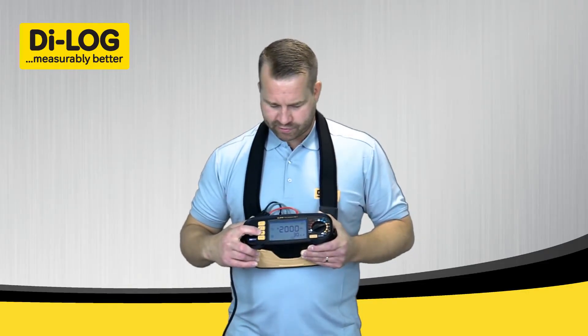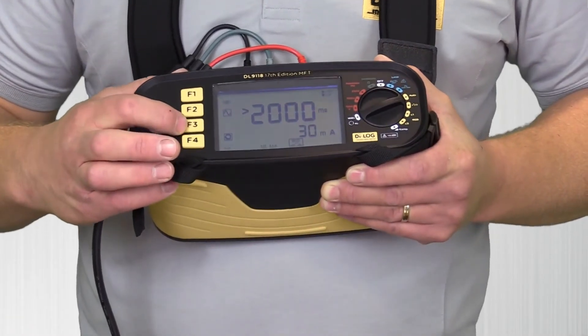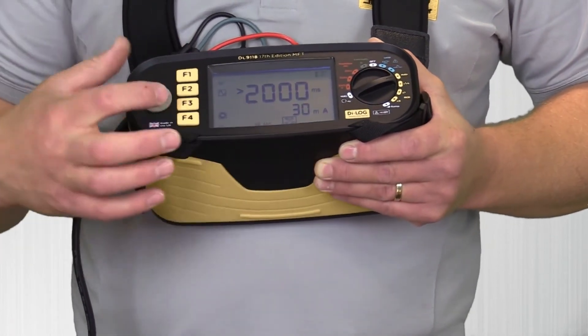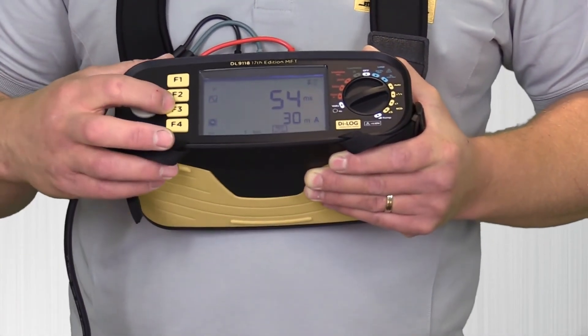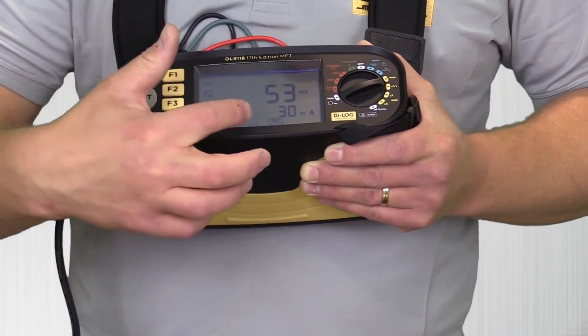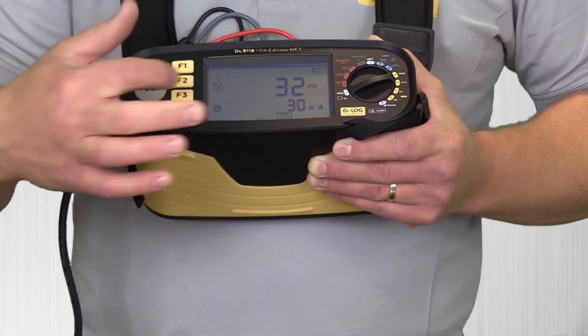From here, by pressing Function 3, I can go through the test results: zero degrees at half the current; 180 degrees at half the current; zero degrees at one times the current — 54ms in this case; 180 degrees at one times the current; zero degrees at five times — 32ms; and 180 degrees at five times.